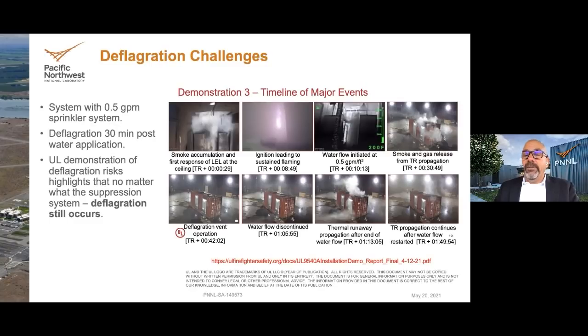But we see that even after about 30 minutes, or another 20 minutes of water flow, there's still smoke and gas release. 42 minutes after the event, there was a deflagration. The water flow was discontinued about an hour after the event, and after the water flow was discontinued, thermal runaway continued. So in this test, there was still gas production and still deflagration.